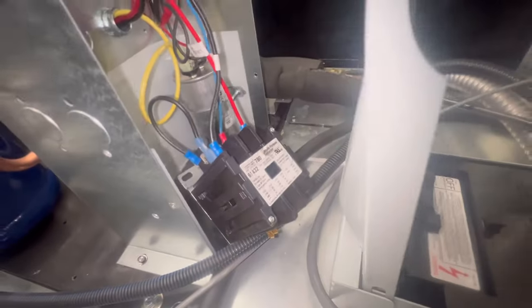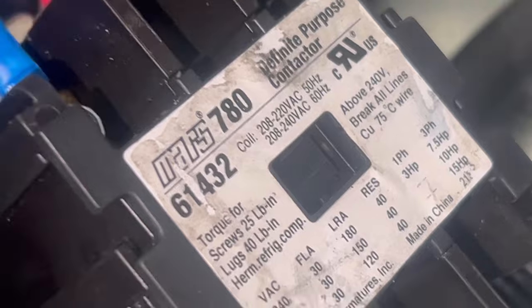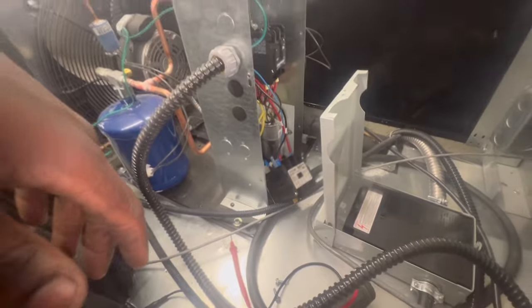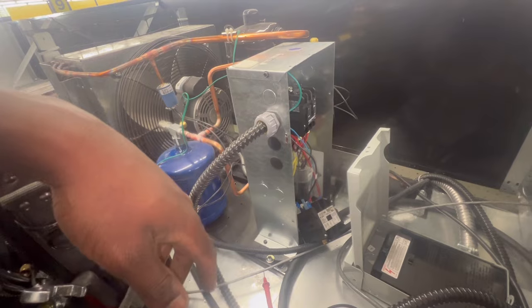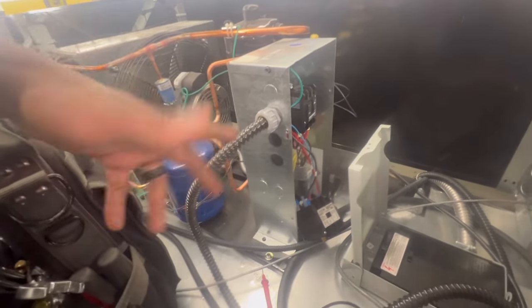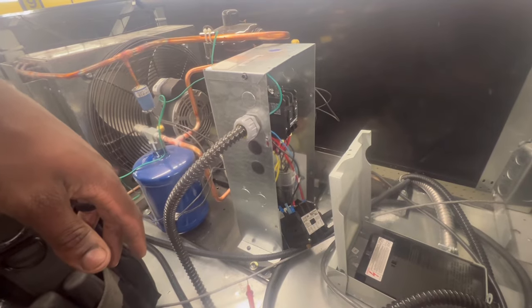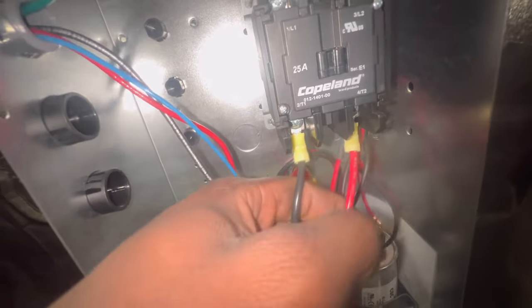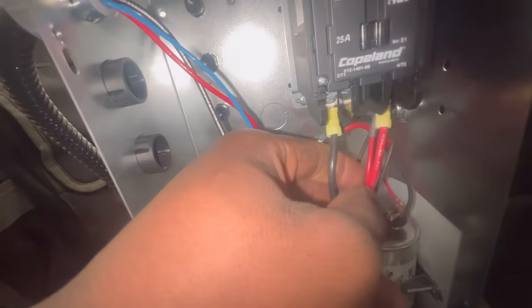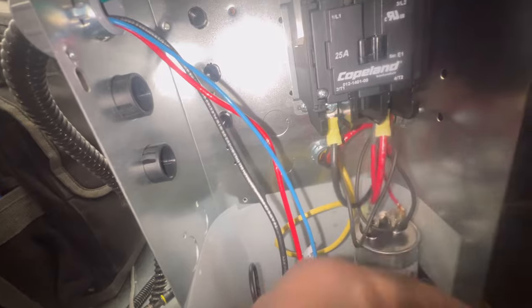Alright, as you can see guys, the coil is not pulling in. So that contactor coil is bad, and I already knew it just off the jump. Like I said, the controller is sending voltage - we have 208 volts to the coil. I'm going to go ahead and change this one out and I'm pretty sure I'm going to change out the next one. Make sure you all wire everything wire for wire. These two wires are for our compressor, and we got our run capacitor on it.